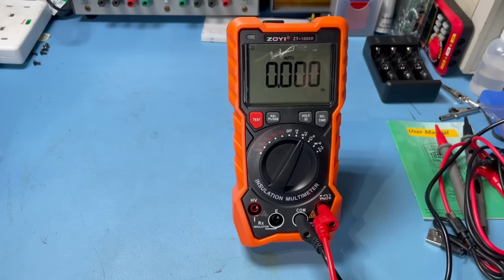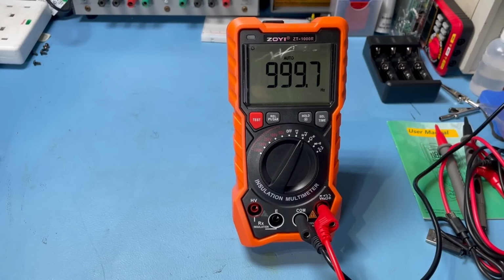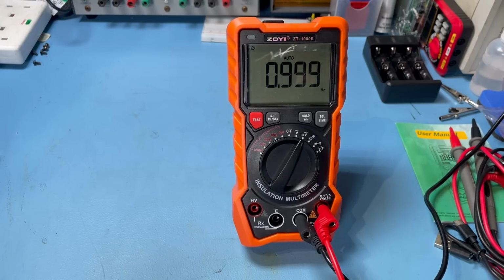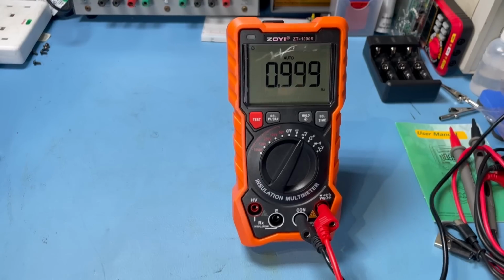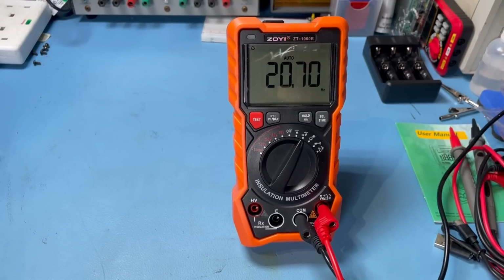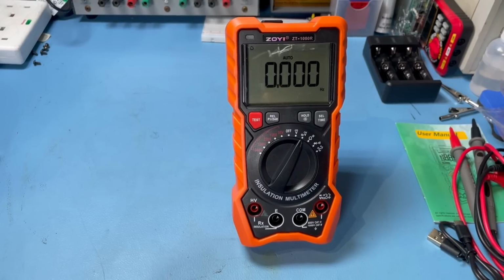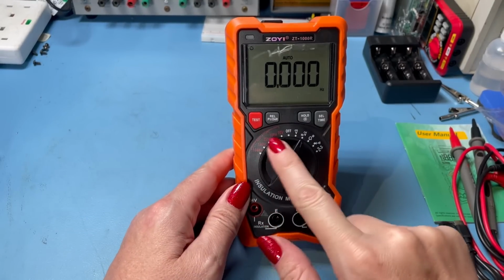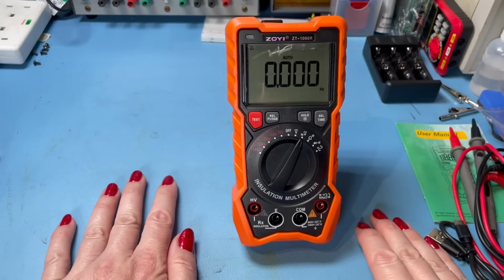Okay, so frequency, let's go for 1 kilohertz. 999.7. 10 kilohertz. Yep. Okay, so pretty good on frequency. It's probably not a function that you're going to use a lot on this particular meter. One of the main reasons you're going to have this meter is for the insulation testing. So we're going to try this in a minute.